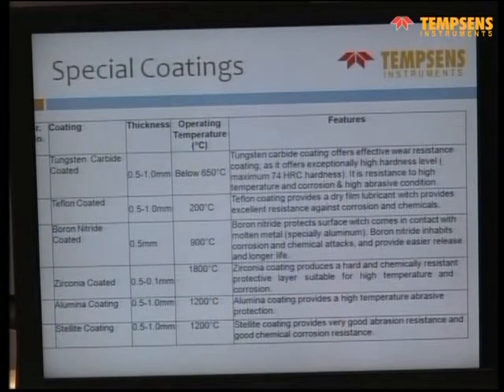Boron nitride coating is for applications in molten aluminum, because boron nitride is a kind of lubricant, so the molten aluminum will not stick to the metal. Zirconia coating is again for high temperature and for abrasive environments. Alumina coating is again for high temperature applications. Stellite coating is again a hard coating for high temperature applications. So all these different kinds of coatings are available for thermowells. Normally they are coated onto the metallic thermowells.